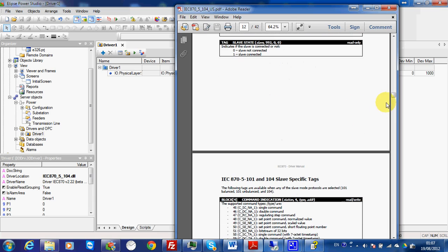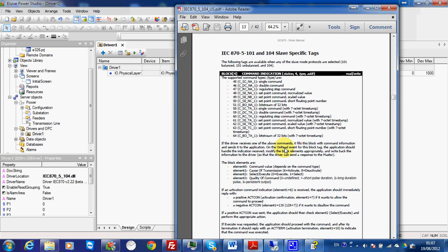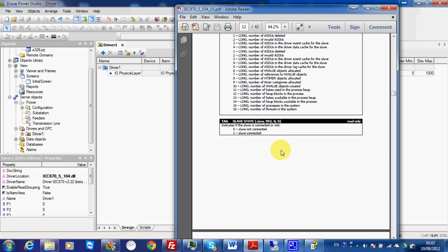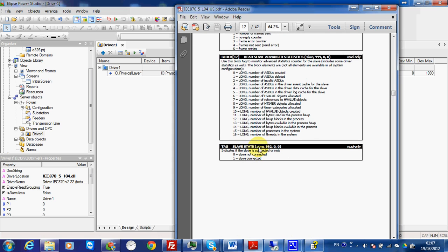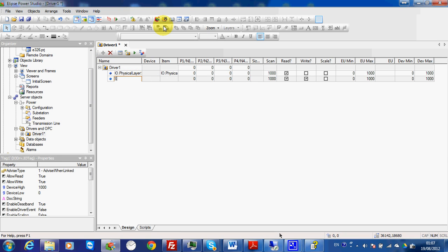For the ASDU, I can use some special tags. For example, I have a test link, a command indication, and a slave state. Let's choose slave state for the demo. I choose N1=992, and then I can read whether the slave is connected or not connected.